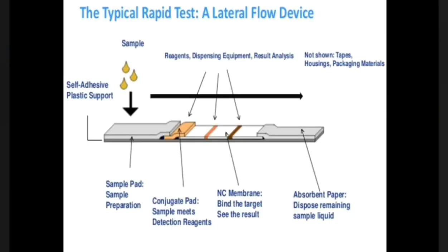The liquid sample used is mostly serum. One very important recommendation is to avoid hemolytic samples, because a hemolytic sample will release free hemoglobin onto the nitrocellulose membrane, resulting in background color that is difficult to deal with. The clear liquid sample moves from the sample pad towards the conjugate pad, then to the nitrocellulose membrane, ending at the absorbent pad through capillary action. Because of this capillary action the sample moves rapidly, and test results are obtained within 15 minutes.